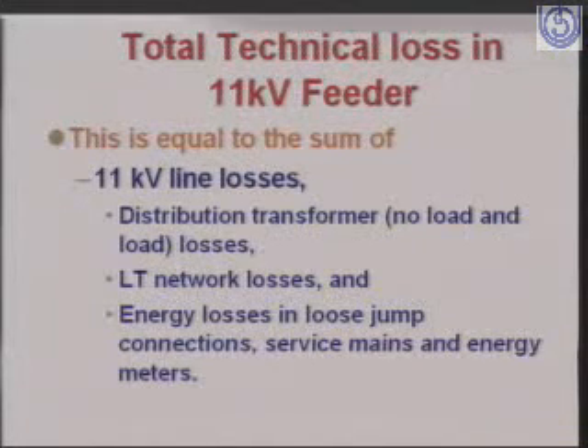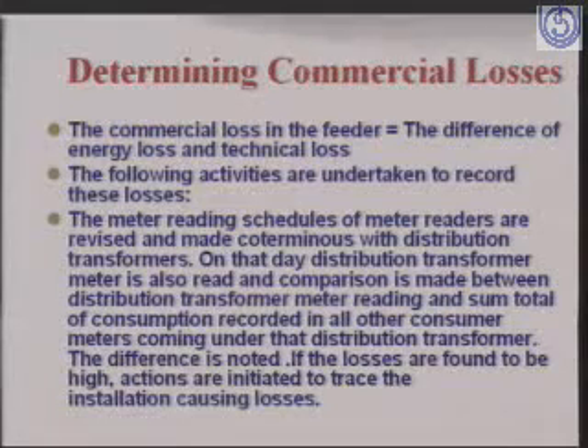So the total sum of technical losses on 11 kV feeder is distribution transformer losses, LT network losses and energy losses in loose jumps connection. So through this approach we are in a position to assess the technical losses. Now let's come to the commercial losses.